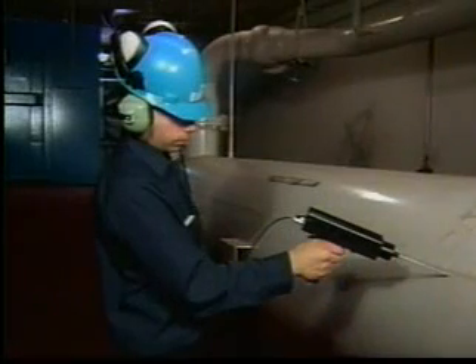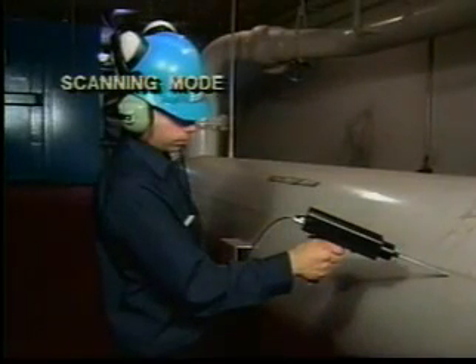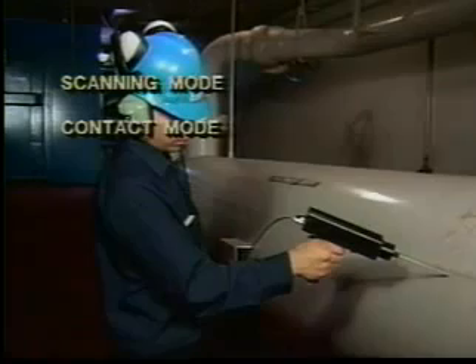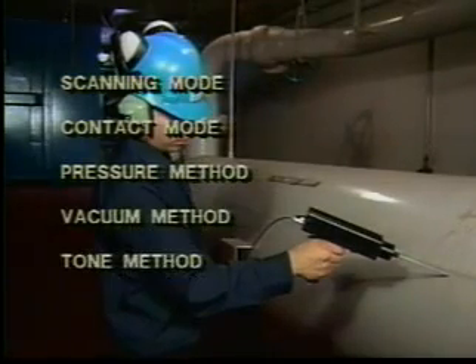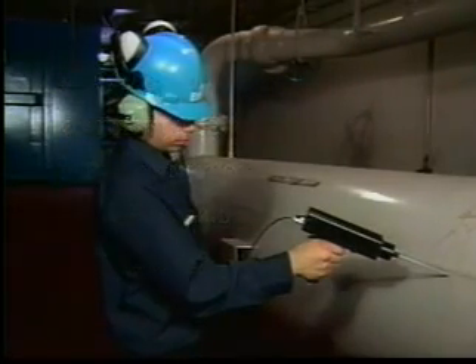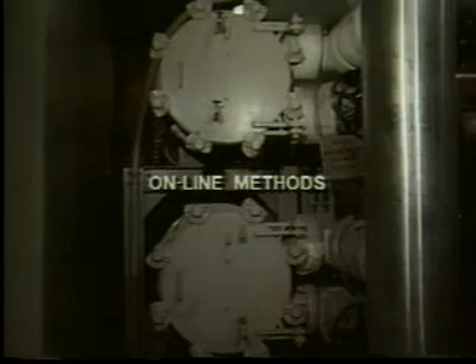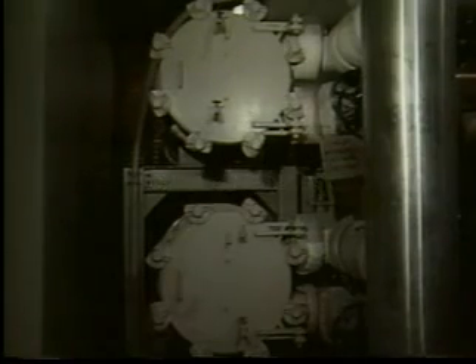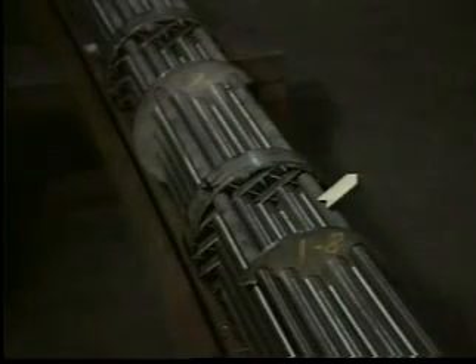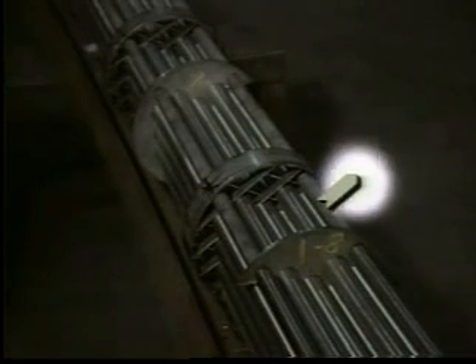The leak detection methods we will use include general scanning mode procedures, using the contact probe, pressure, vacuum, and tone methods. In an online environment with equipment under pressure or in a vacuum condition, a leak will move from the high pressure side to the low pressure side, generating a turbulent flow with strong ultrasonic components. These sounds are detected with the Ultraprobe using the scanning or contact mode.